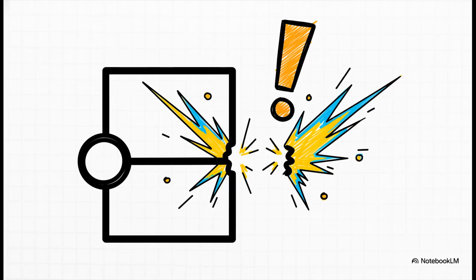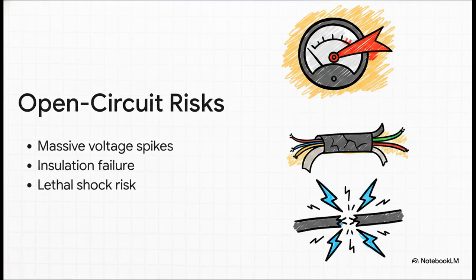Before we go any further, I need to hammer home a critical safety note. You must never, ever leave a CT secondary open-circuited while the primary is energized. Why is this a literal life or death rule? If you don't give that secondary current a path to flow, the physics turn violently against you. The voltage across those secondary terminals won't just sit there quietly, it will massively spike to thousands of volts. We're talking instant insulation failure and a very real risk of a lethal shock to anyone nearby. It's absolutely crucial to remember this.